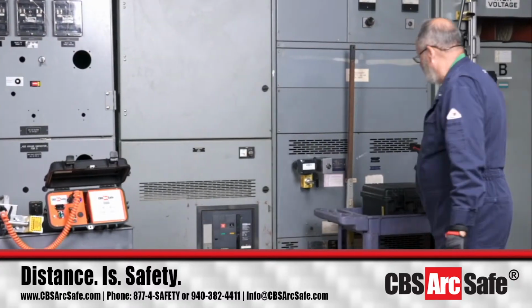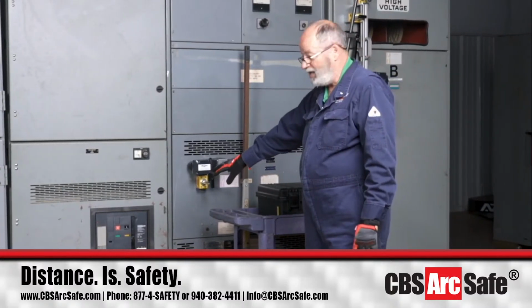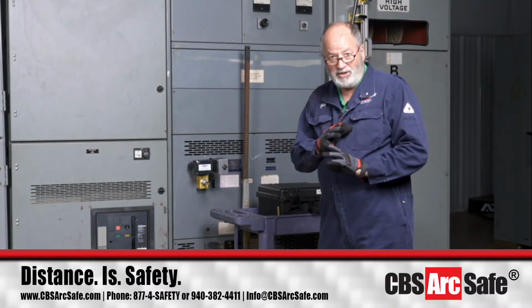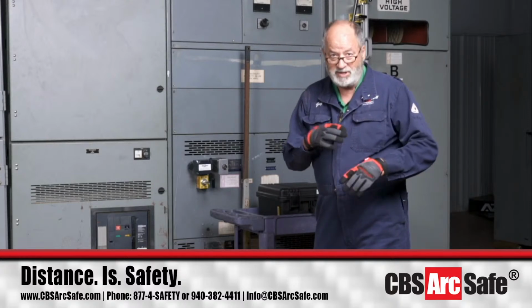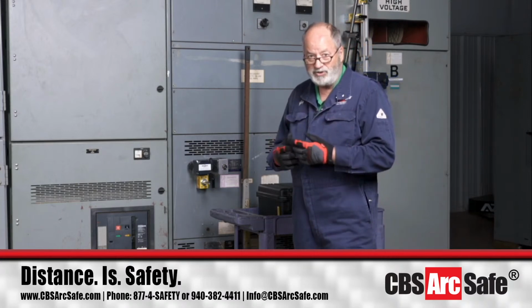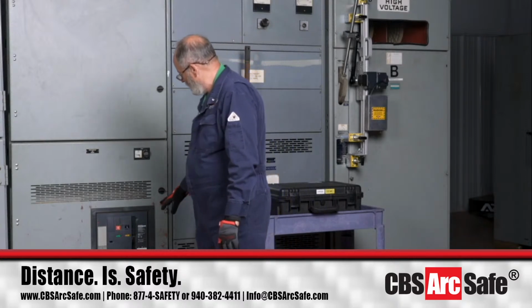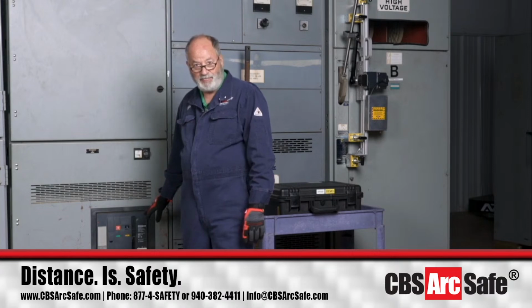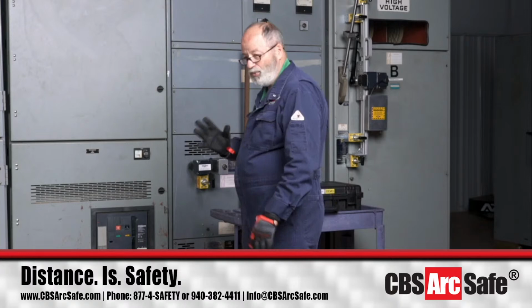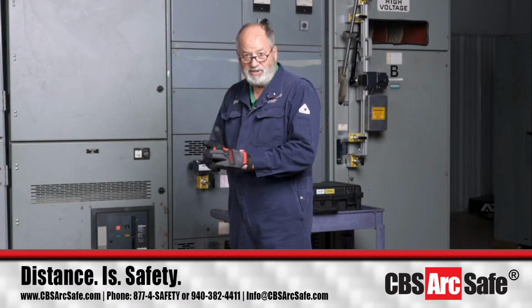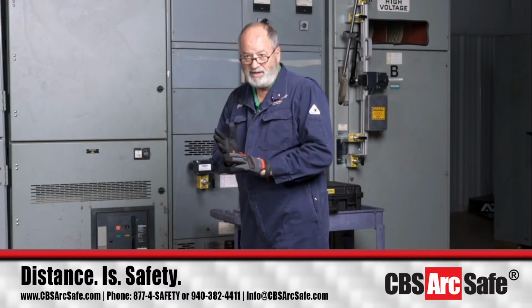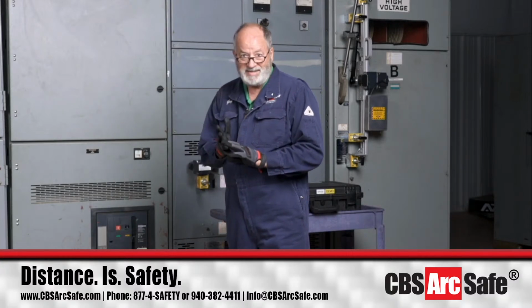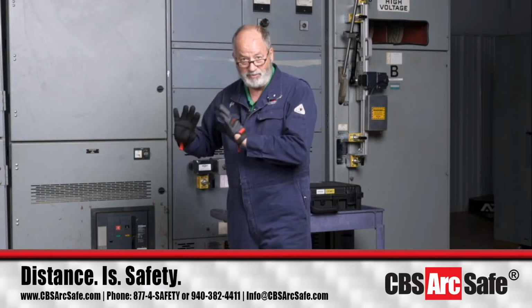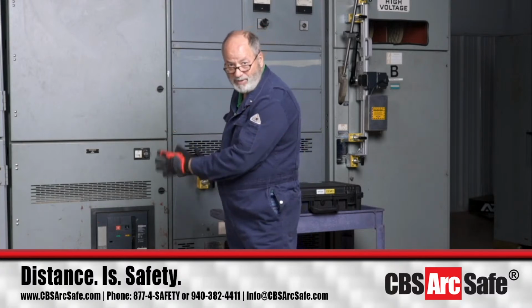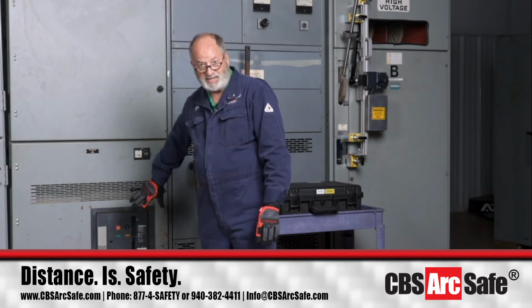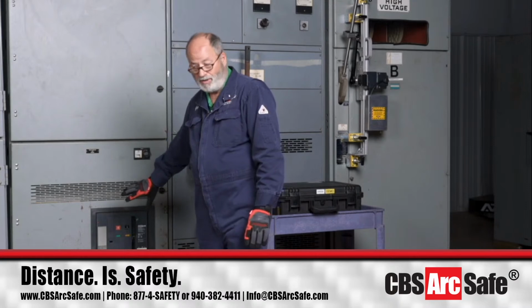Now, the next thing we're going to show is the NW20, and this is going to close and trip the NW breaker. The Masterpact series of breakers was originally made by a company called Merlin-Gerin in France, which merged to become part of Schneider Electric. When SquareD became part of Schneider Electric, they took the MP version and made the NW, and now the current generation is MTZ. The nice thing about the NW20 is it will work on the MP, the NW, and the MTZ larger frame breakers. The NW, all their frames will work. The NT, which is a small frame breaker, uses a different remote switching kit because it has a different face shape. So when I say large frame, I'm talking about something with this size face. We're specific about geometry here.